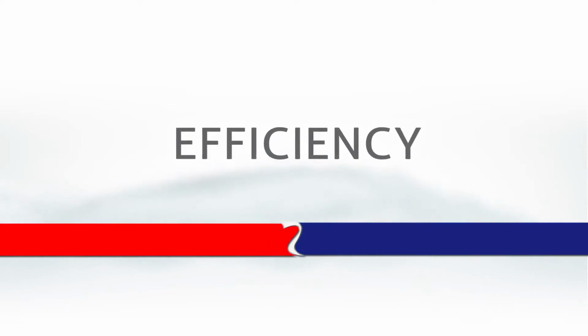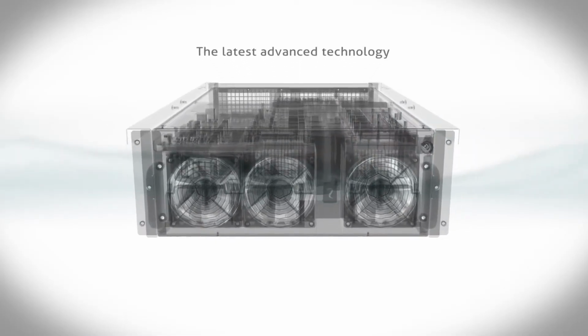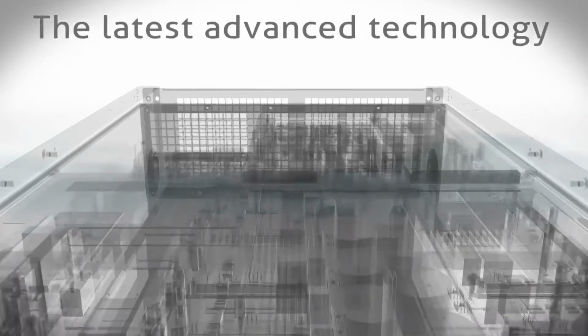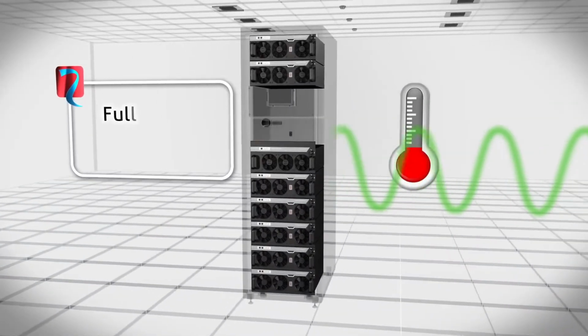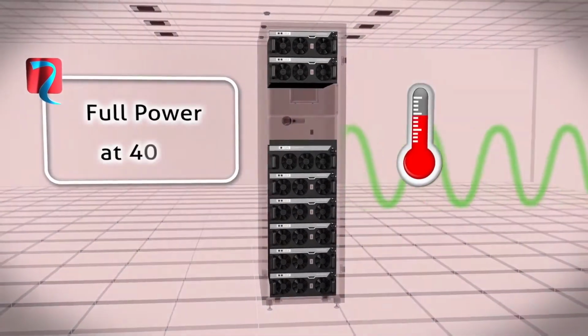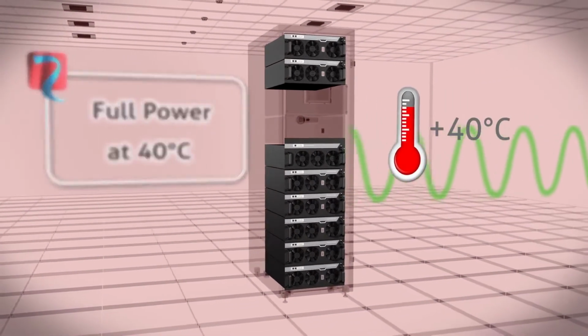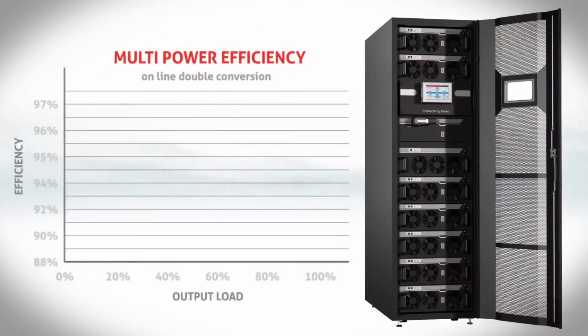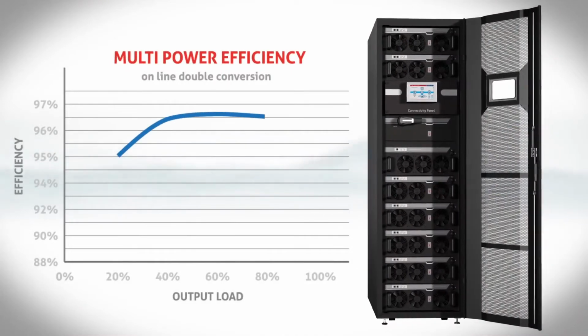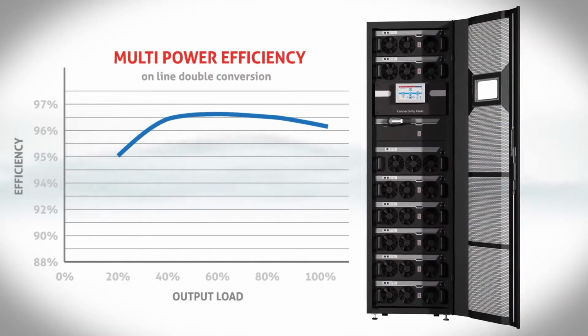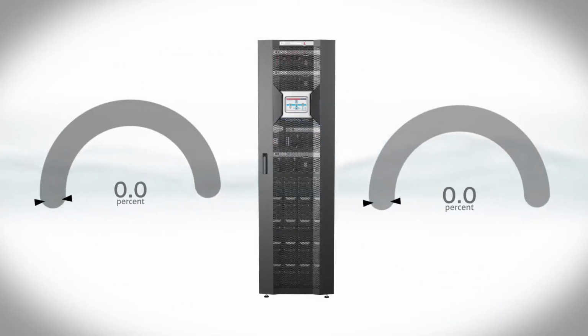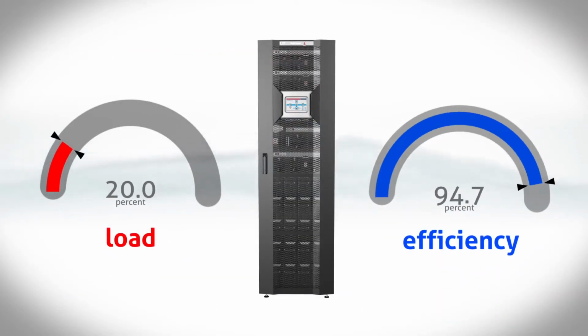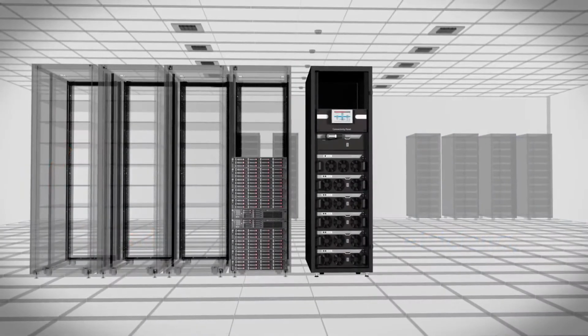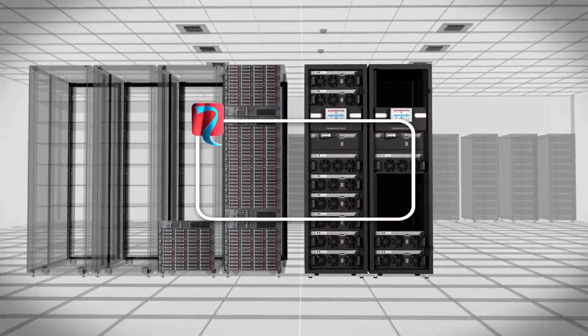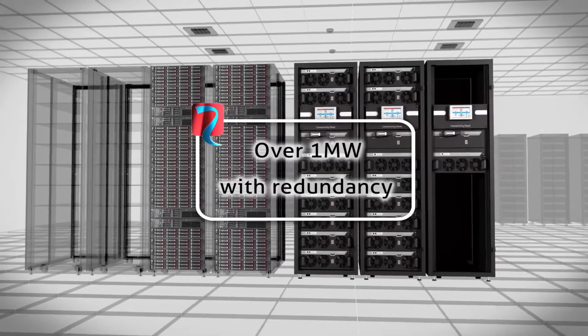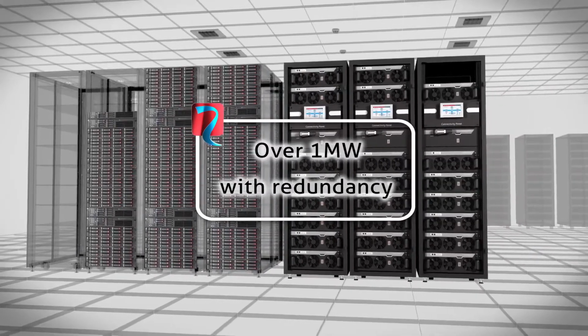Efficiency. The power modules utilise the latest advanced technologies which guarantee full rated power even with unity power factor loads, without any power downgrading. This is even up to temperatures of 40 degrees. The multi-power offers 96.5% system efficiency when operating in online double conversion mode, with an outstanding performance of over 95% whilst operating at 20% load. This superior performance ensures extremely low losses at any load level whilst maintaining a true modular solution for any changing data centre environment in terms of power demands.